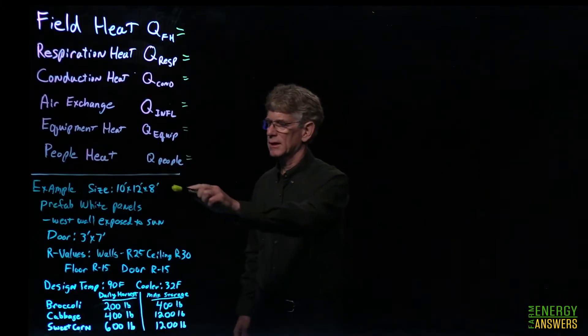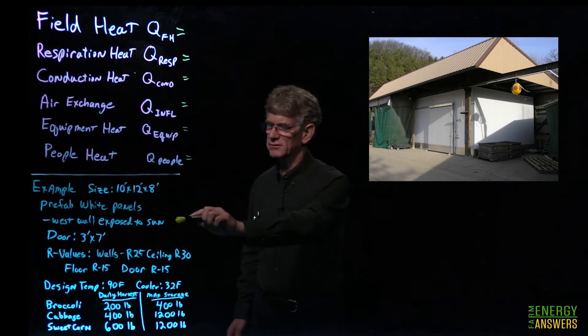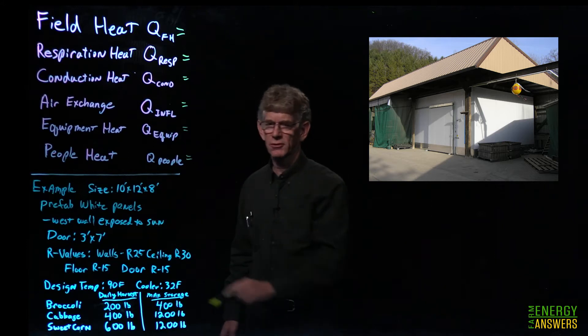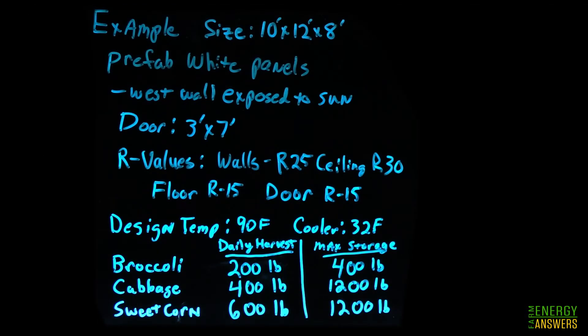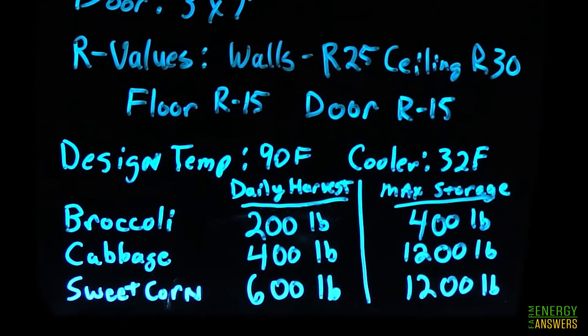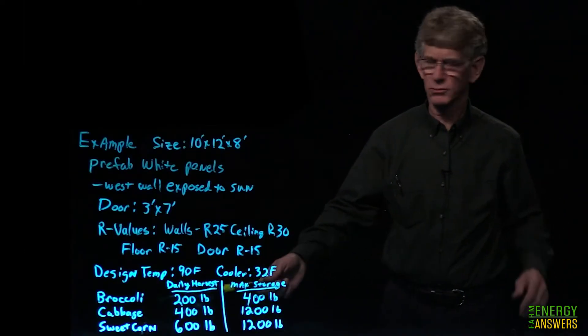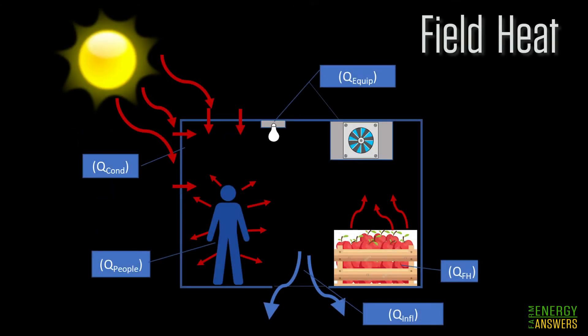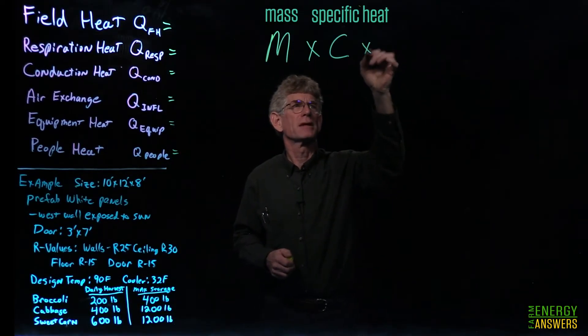To help us understand this, we're going to use an example. The example is a 10 by 12 by 8-foot-high cooler made of prefab white panels. The west end is exposed to the sun; the rest is within a building. It has a 3 by 7-foot door. We have R-values for the panels, and our design temperature — typically worst case — will maintain 32 degrees inside, because we're storing broccoli, cabbage, and sweet corn, which are best kept at that temperature.